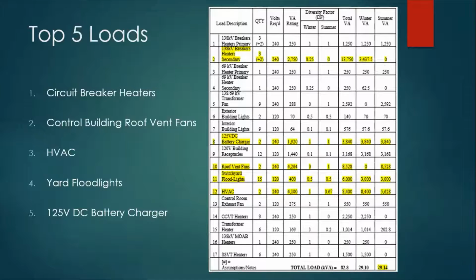Loads such as transformer fans have a diversity factor of 1 in the summer to maintain operating temperature, but it is reduced to a factor of 0 in the winter when sub-zero days are common. A table was compiled that listed 17 major AC loads that were considered, as shown on the table on the right, covering the equipment, quantity, diversity factor, and the resulting demand.